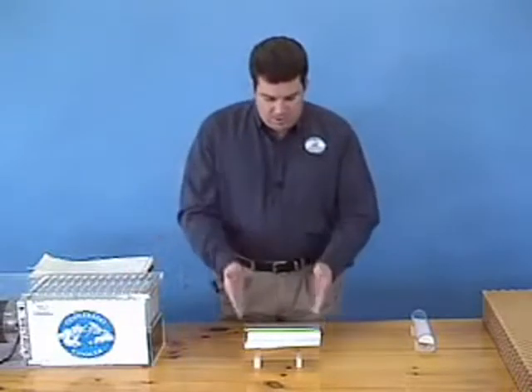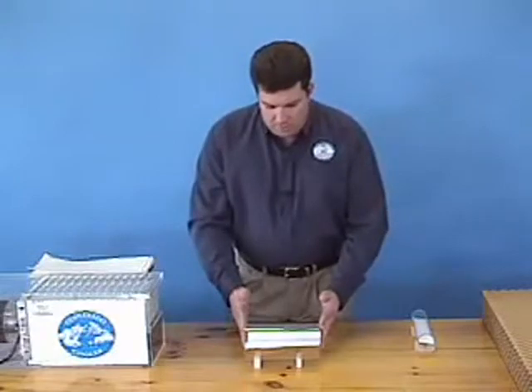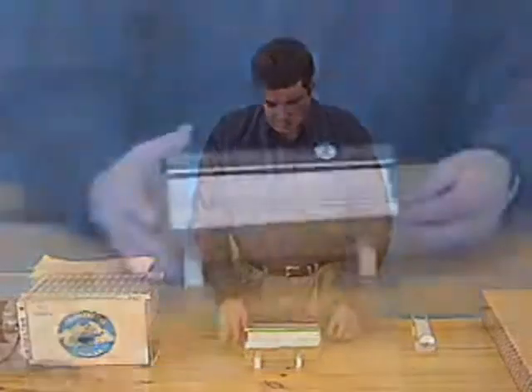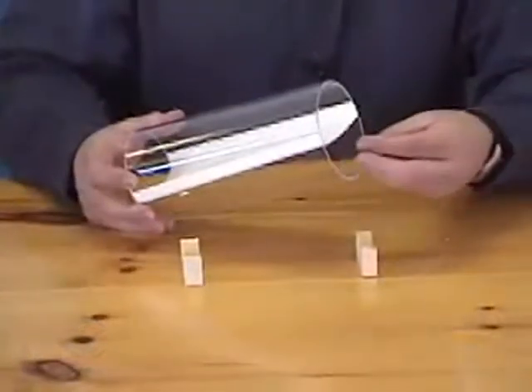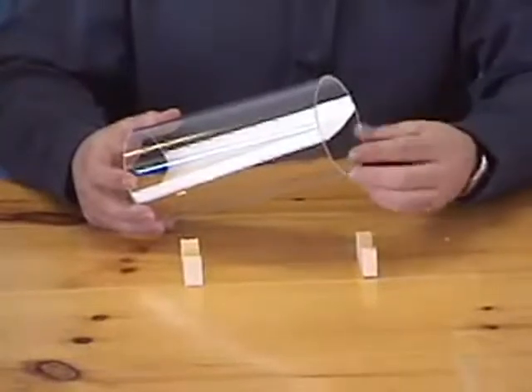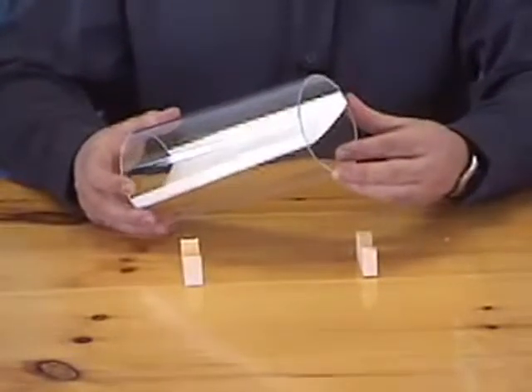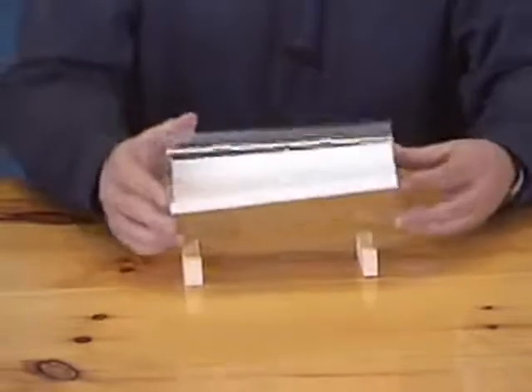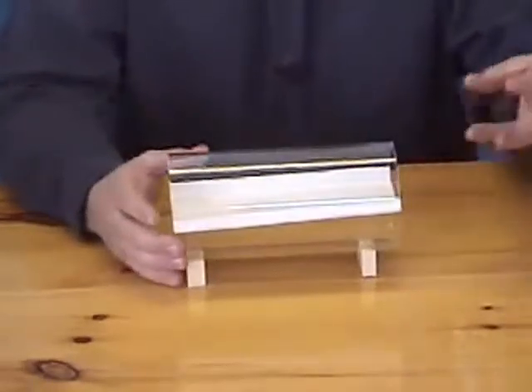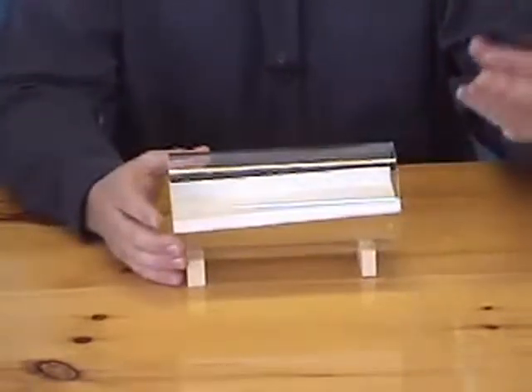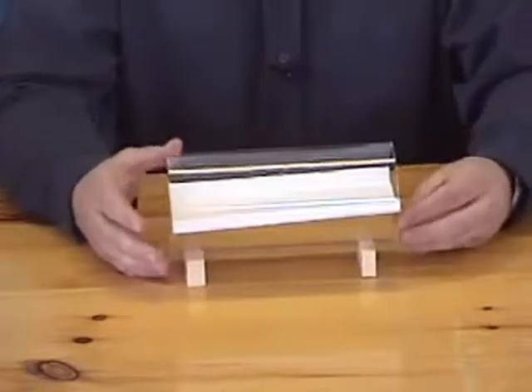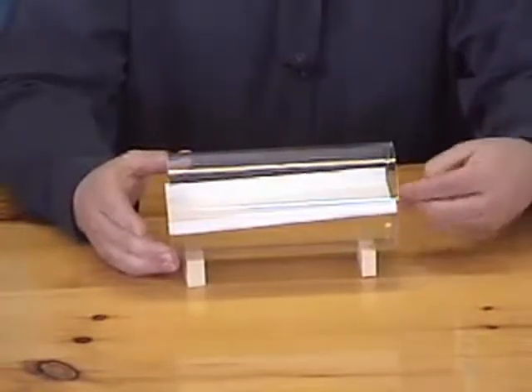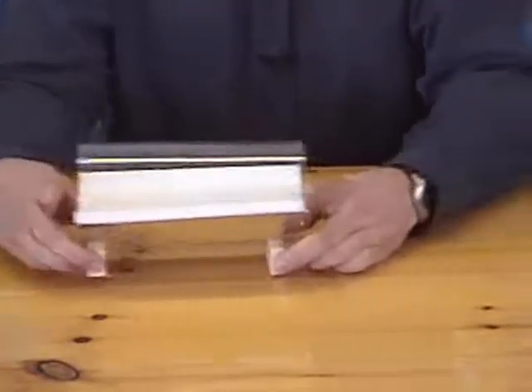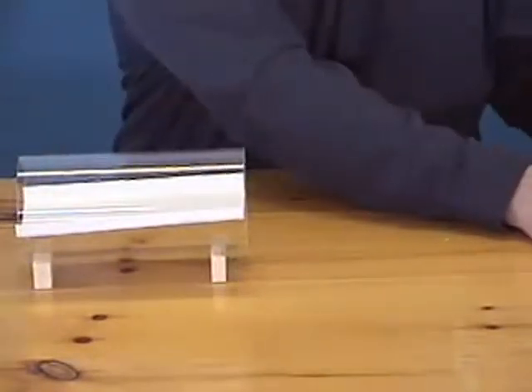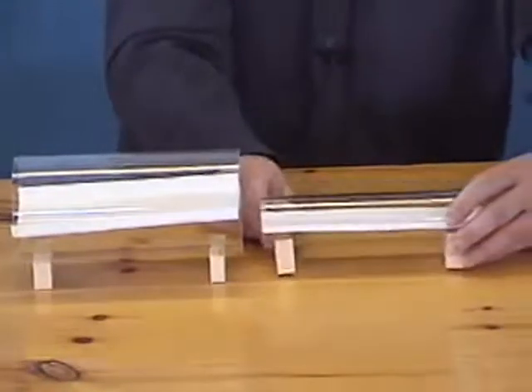Let's go back to your theoretical long tube heat and mass exchanger. When the air comes out of the dry side of the pipe, it will be cooler, and its wet bulb temperature will have been lowered. You'll throw away the humid air from the wet side to the atmosphere. Then you'll take the dry side airstream, and you'll run that down yet another one of your heat and mass exchange pipes.